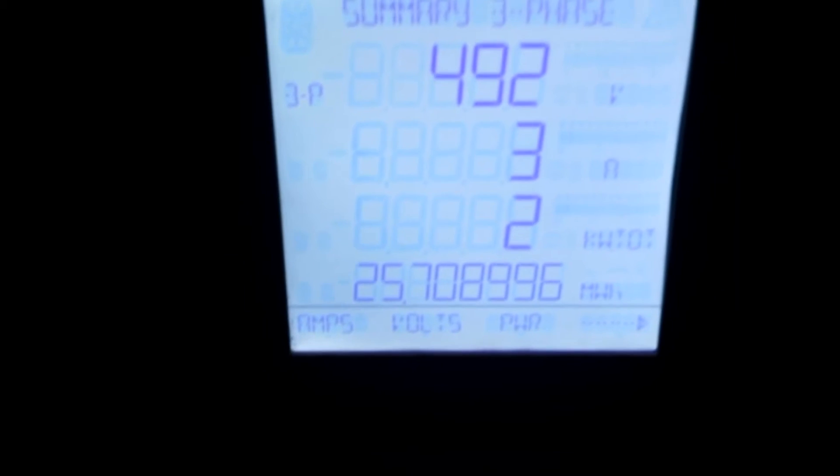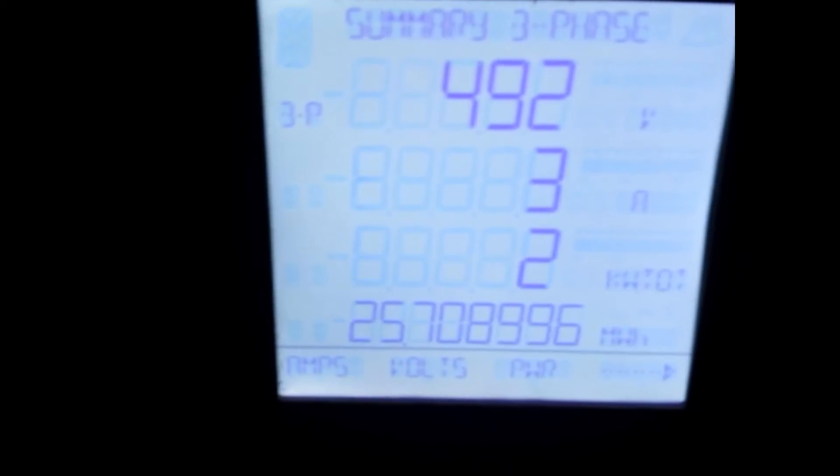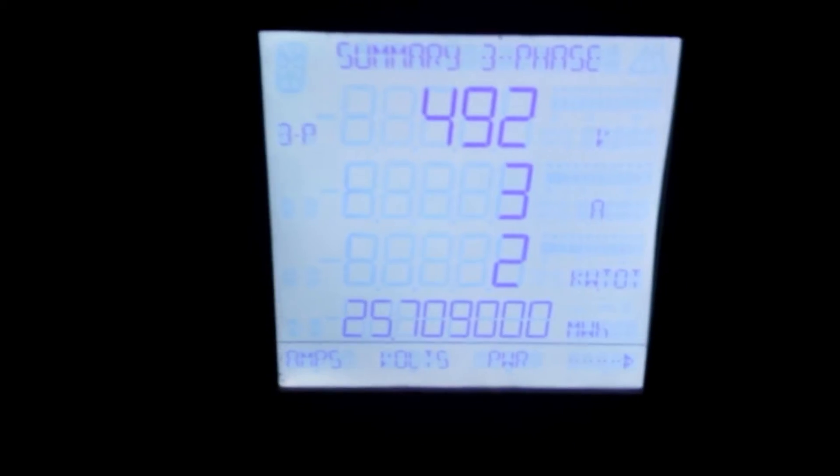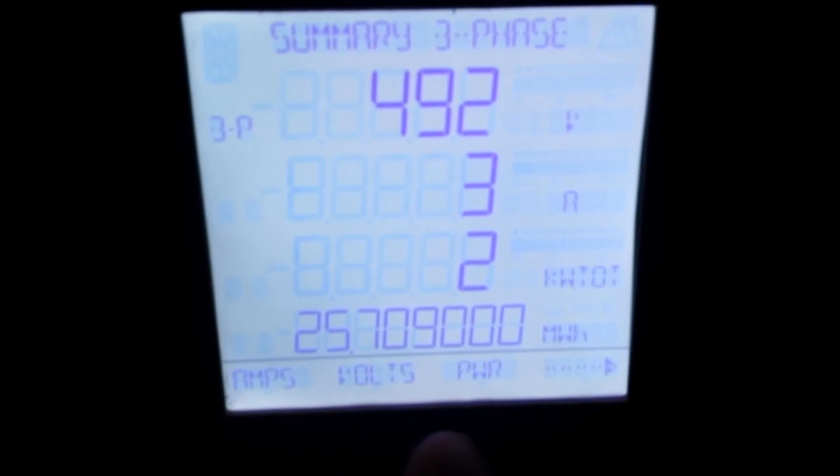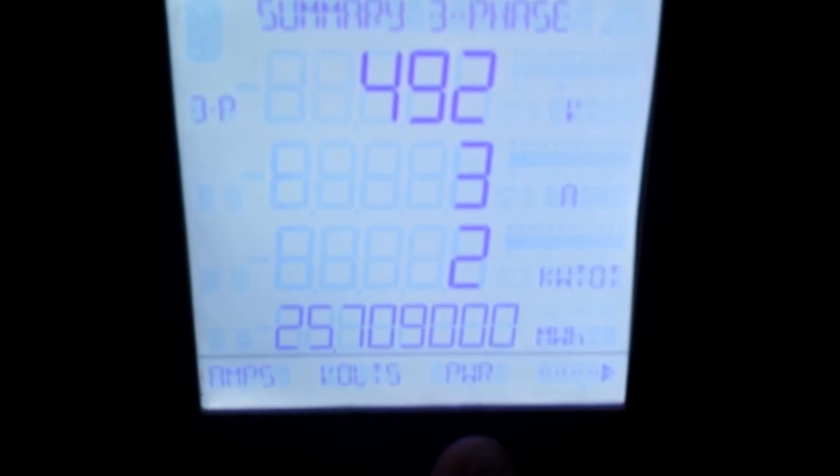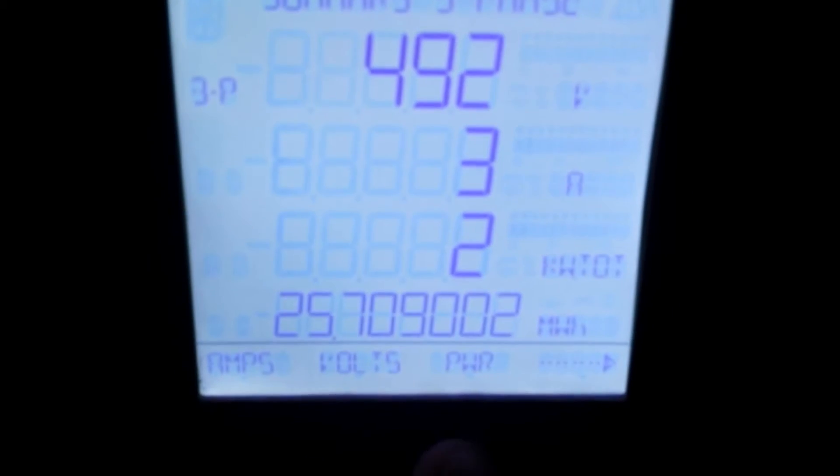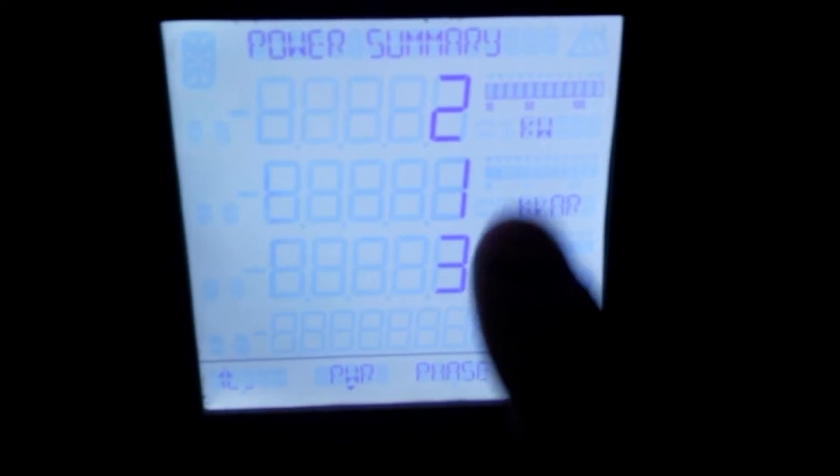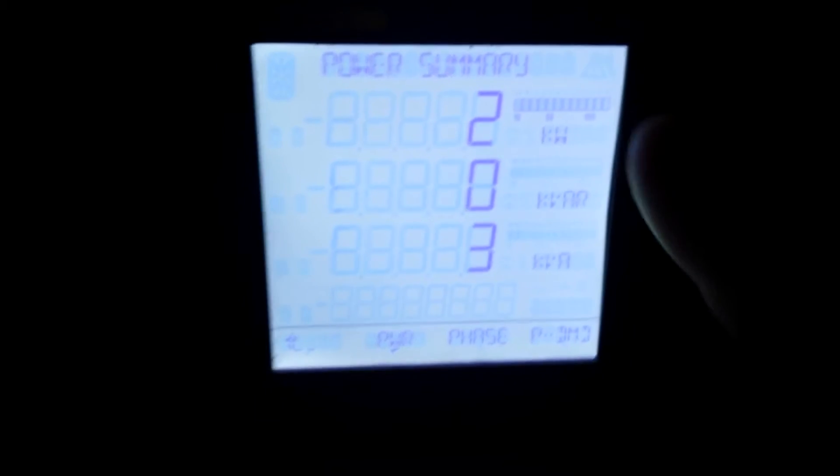Now we're going to compare the readings from the meter to what we are currently showing on our Metasys extended architecture system. What I'm going to do is simply press the power button. It shows me that we're currently using 2kW, and now we will compare that to Metasys. It just went between two to three, so we'll just compare those.